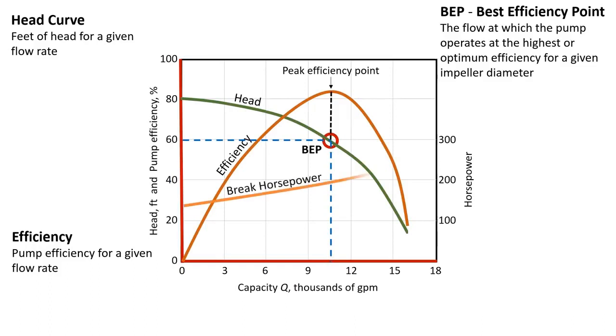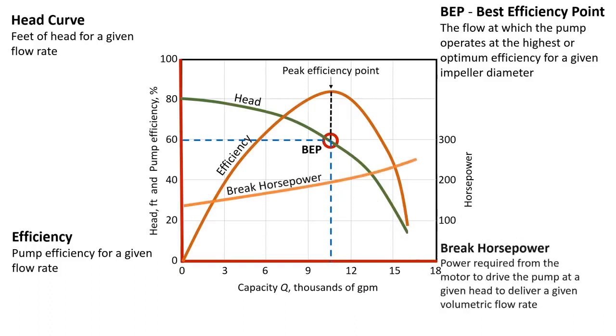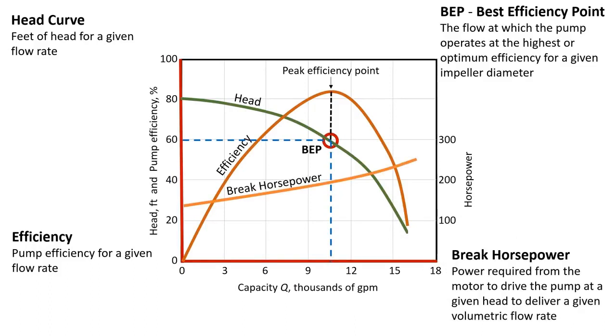If we put the brake horsepower curve on here, we can see the power requirements. Brake horsepower is the power required from the motor to drive the pump at a given head to deliver a given volumetric flow rate. Drawing a line from where the flow rate intersects the brake horsepower curve, we see that this requires about 200 horsepower.